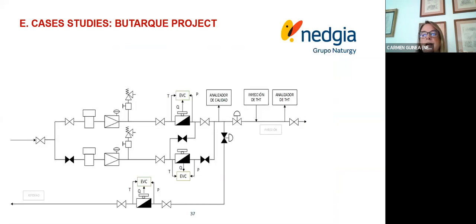This is the process diagram of the gas entry unit. It has 2 lines for regulating and measuring the biomethane flow. Each line consists of a filter, a regulating system, and a fiscal flow meter. The other line is for returning the biomethane when it's rejected due to its quality. The rejection is to the gasometer.